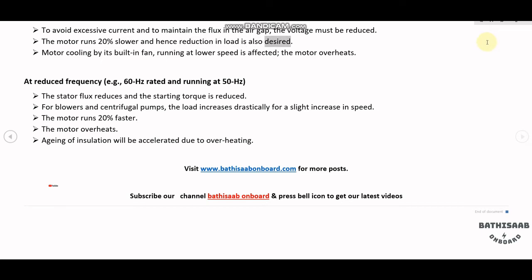Motor cooling by its built-in fan running at lower speed is affected. At reduced frequency — for example, 60Hz rated and running at 50Hz — the stator flux reduces and the starting torque is reduced.